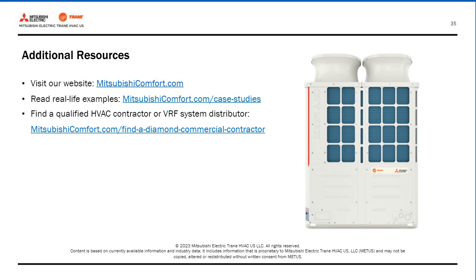The numbers we publish as a manufacturer are conservative, and with every winter blast that happens up in the central U.S. and Northeast, we get more reports of systems operating at negative 12 and the like, and pushing out 120, 115 degree air. So the cold climate heat pumps continue to evolve and be developed to be a sole source of heat, even in very extreme cold temperatures. That's not to say that we don't support backup heat and emergency heat, especially in those types of extreme cold climates. But the systems are being designed and evolved to be a sole source of heat in very cold climates.